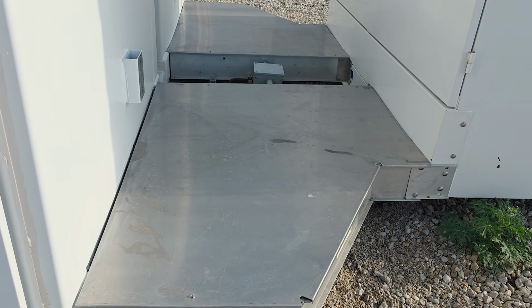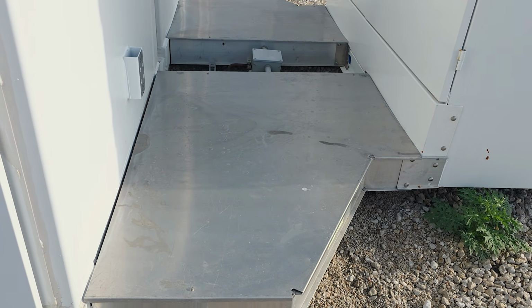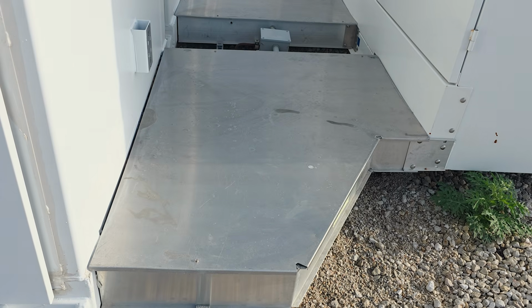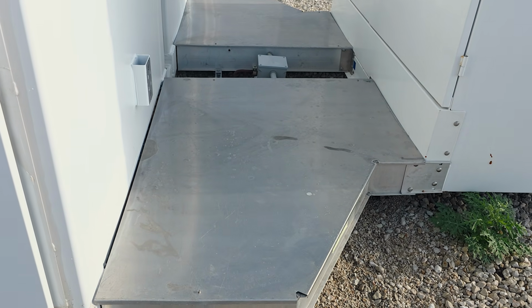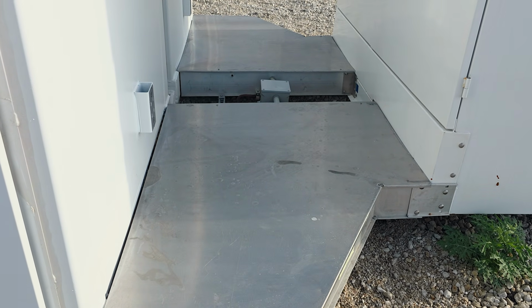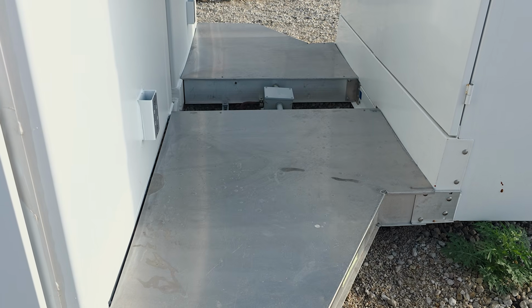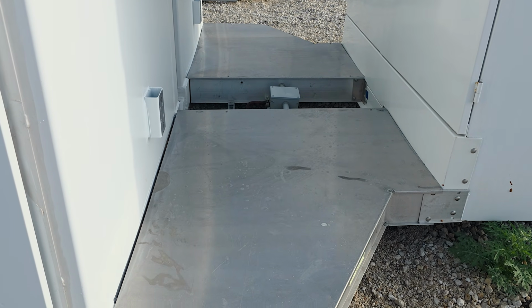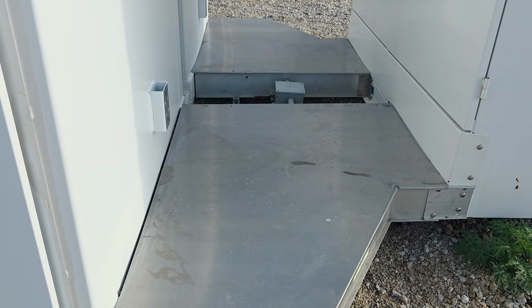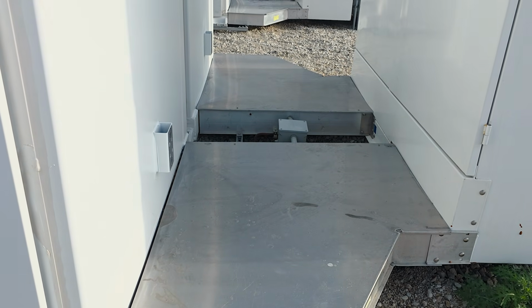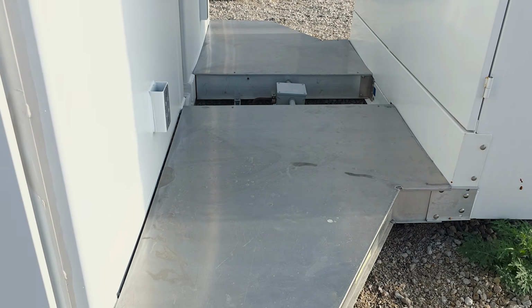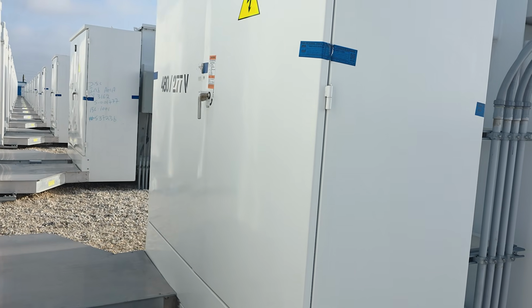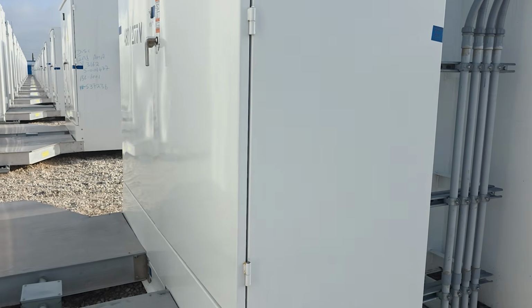So these come out from the inverter, and these are simply just little cable trays, but there are, I want to say, 21 total sets of cables in here, and it's 480, 600 volt cable. I believe it's 750 aluminum, and all of that power, AC power then, goes in the transformer here.